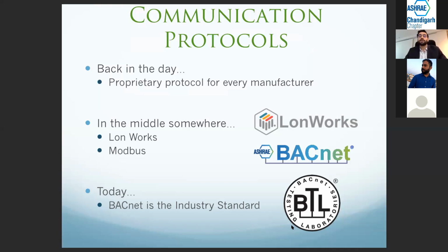Initially, we all moved to a protocol called LonWorks, or LON, you may have heard. And even over the years, ASHRAE has stepped in and said, hey, look, this is what we've been doing with BACnet, and this is going to be the new industry standard. So in today's world, any new installation is typically a BACnet communication protocol, and it is the industry standard.